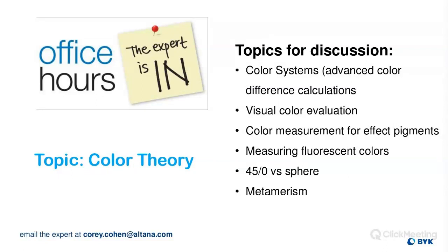If we're talking about non-fluorescent colors, it doesn't really matter what the spectrum of the actual light source is, because that can be calibrated. Whatever the spectrum is, it can be calibrated. The important part is to have enough power at each wavelength to get an accurate measurement.